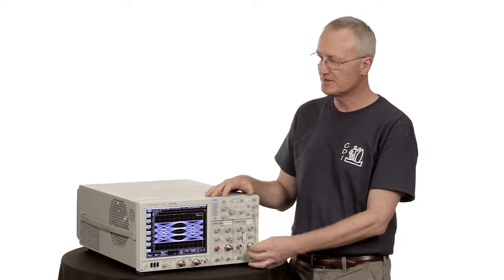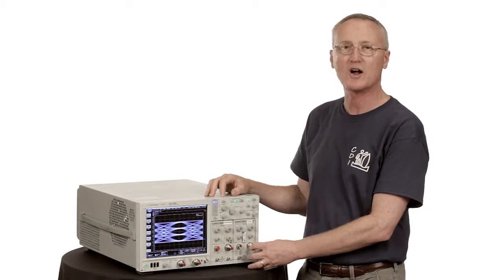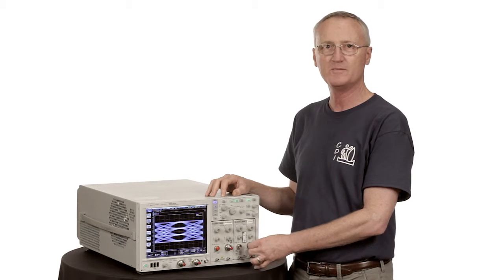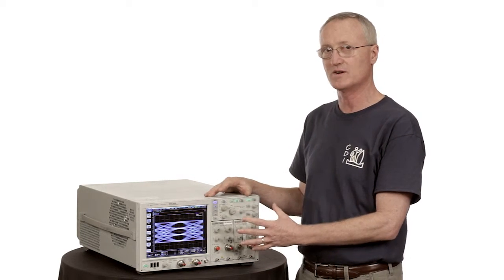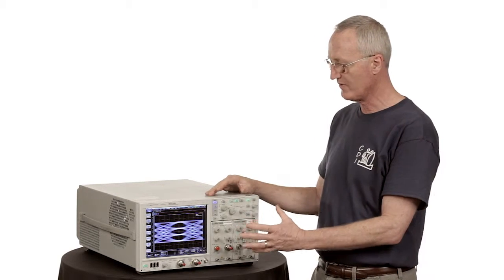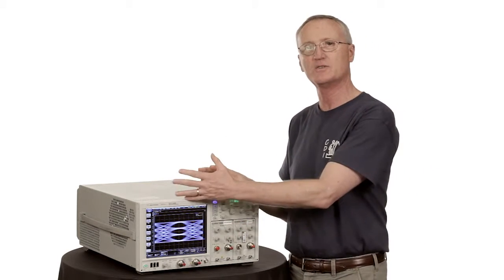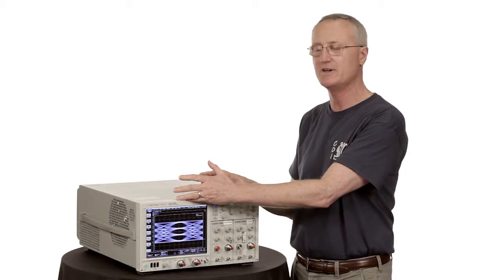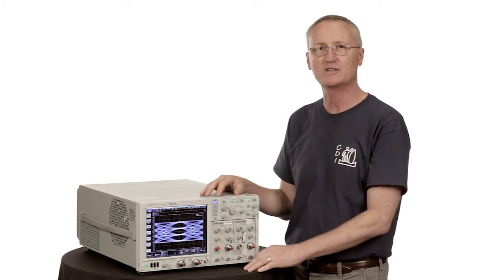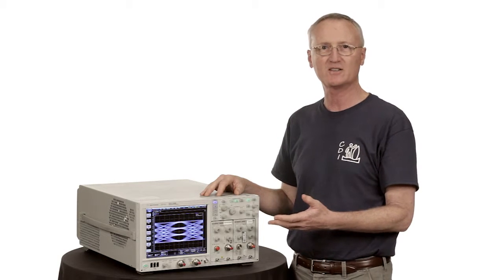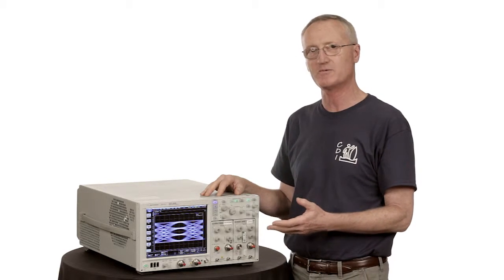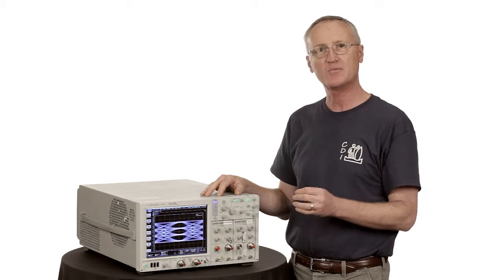There are certain measurement scenarios where clock recovery is required, and in a sampling scope that is done in hardware, not software. So we've got different scenarios. We have external accessories that do clock recovery. We have modules that have clock recovery built in. What would we have to do to change that clock recovery hardware to work with a PAM-4 signal? It turns out not much.